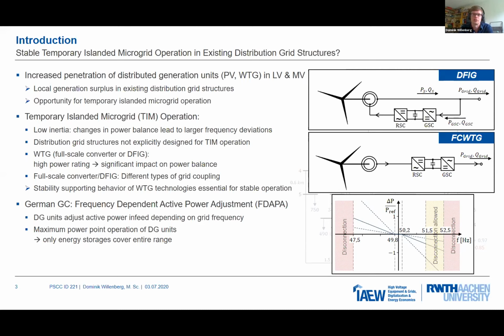So when we have a look at the bottom right side of the slide, we see, let's say, the frequency shown over the active power. And when the frequency changes, the active power needs to be reduced or increased. This figure on the right side is only applicable for energy storages, since they are able to consume power from the grid. So if we just think about generation units, due to the usual operation at the maximum power point, only in over frequency situations are they able to reduce the active power.